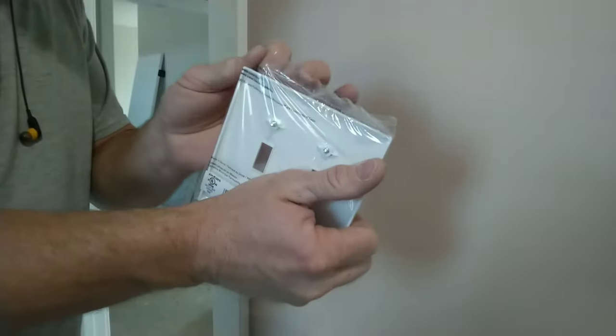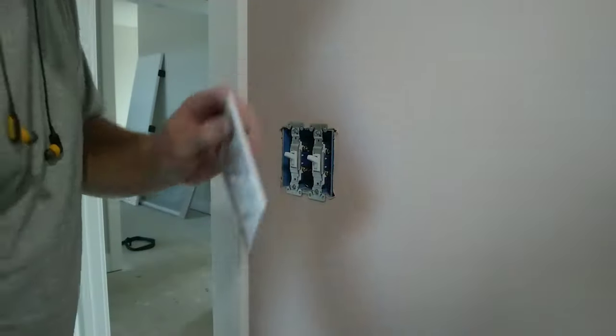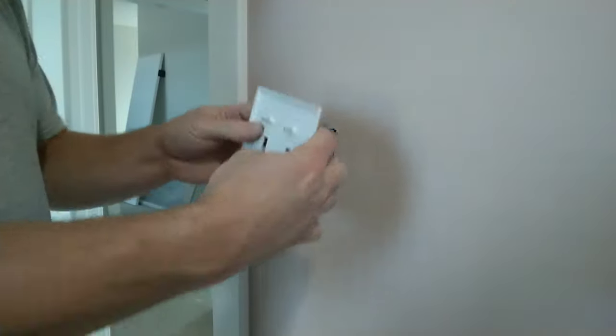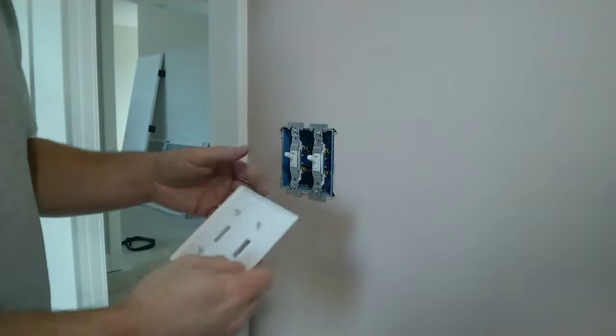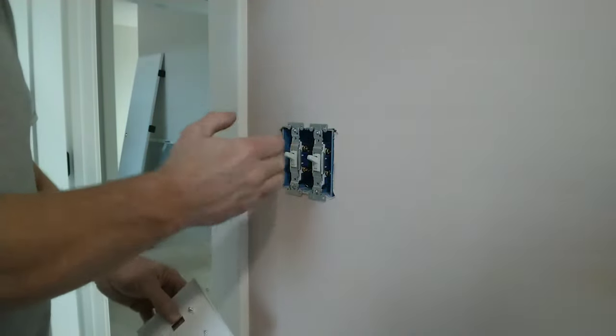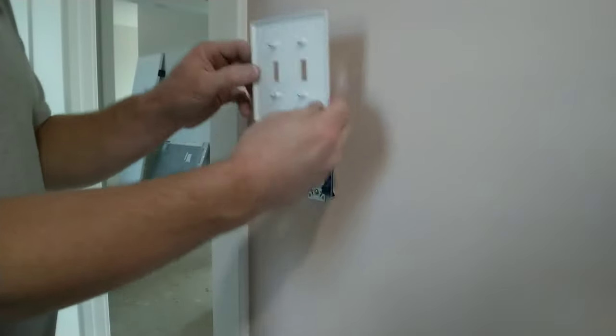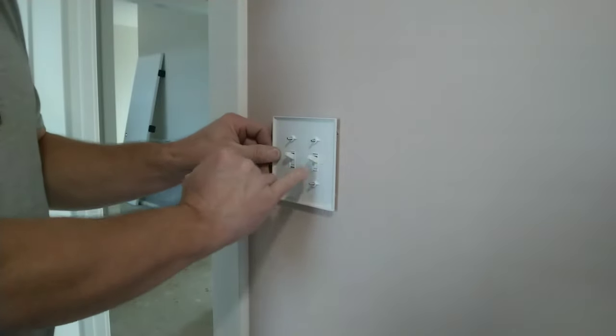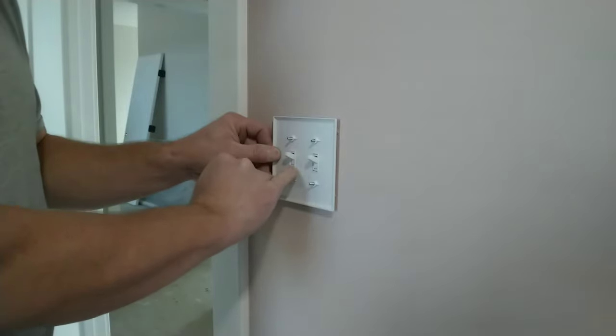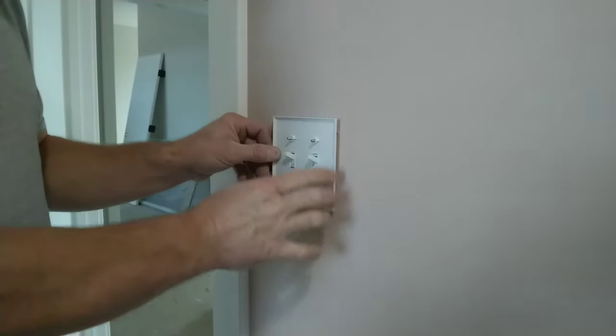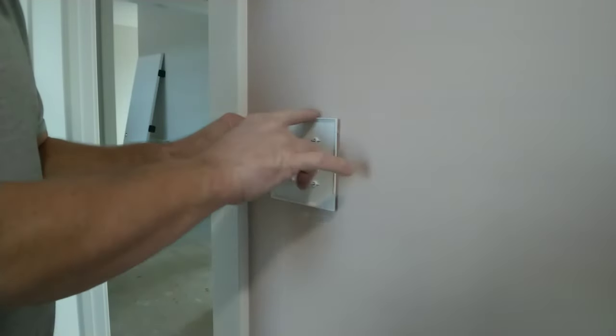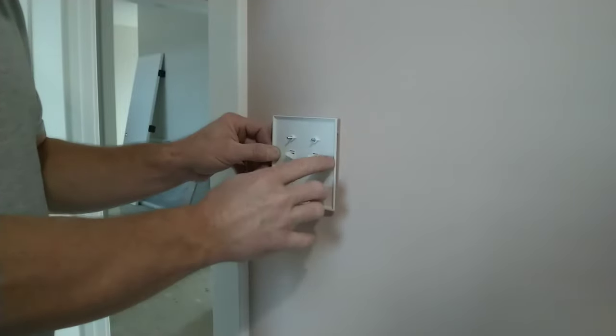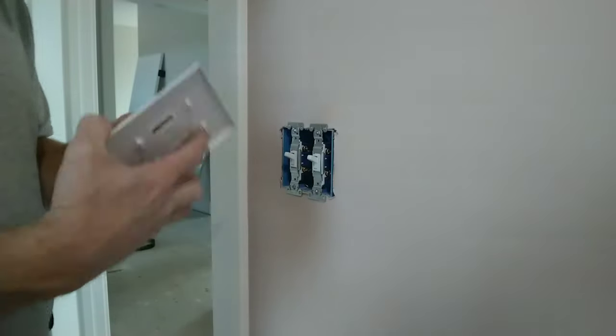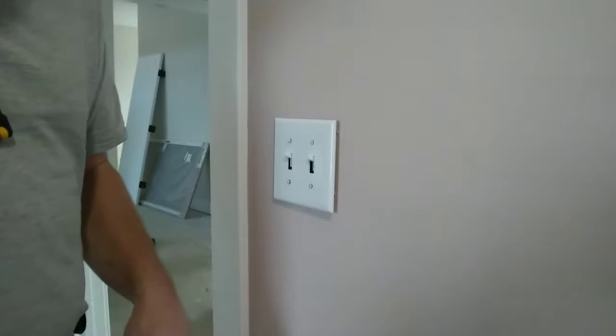Like I said, grab your package on the corner, pull down, no utility knife needed. Same way as a single plate, but now we've got an alignment issue. We're gonna find out if this is aligned properly, and if your box and your stud is aligned properly and everything looks level and square. First thing I do is put this on backwards, and then you can look at your spacings as you're holding this. You can also look horizontally and vertically and see if this is level and square. Now that I've got it horizontally level and the spaces are evenly spaced, I take this and flip this around. I hang it onto the switches.